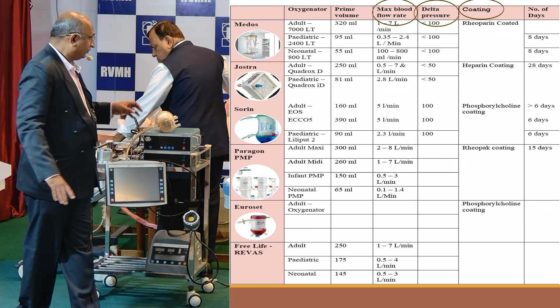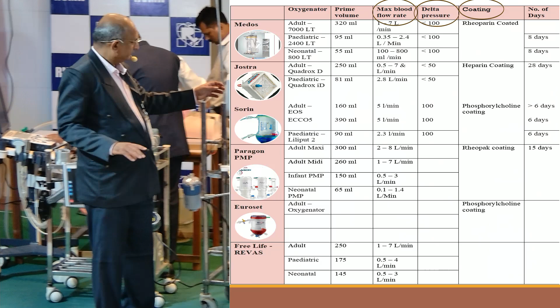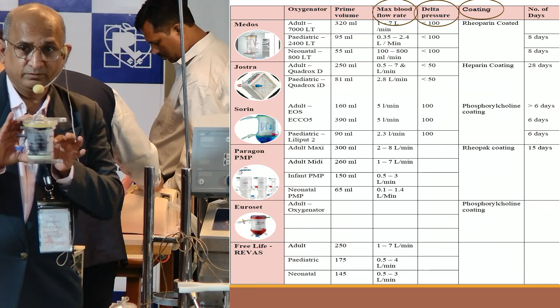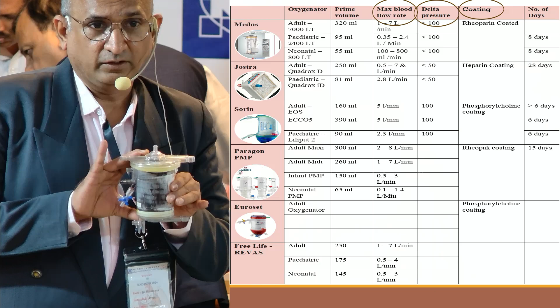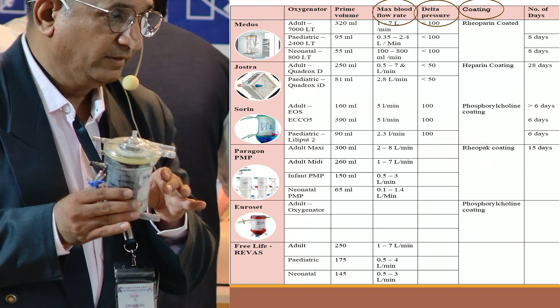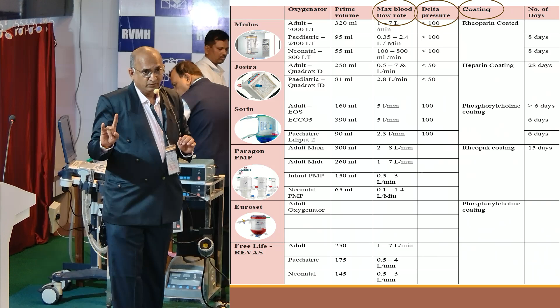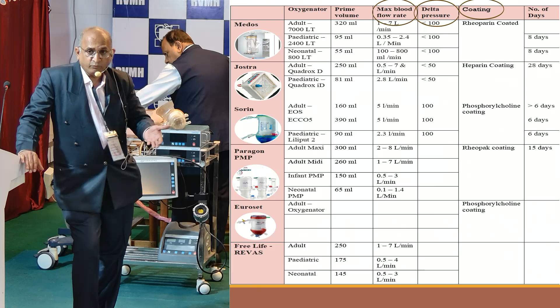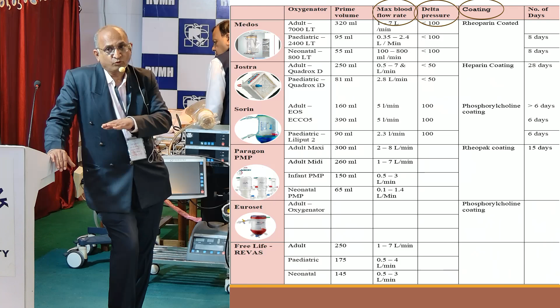So you have to use the appropriate oxygenator. For example, as I showed you, a pediatric oxygenator. Suppose you want to support neonates, you require such a small oxygenator. You don't require a big oxygenator, and it can support you for 800 ml. This can be used even for ECMO, because in ECMO we are not going to go above 500 to 800 ml of flow. So this is good enough for that. But if you want 1.2 liters of flow, you can't use this. Then you have to put one more oxygenator. Most of the PMP oxygenators have a rated capacity of 7 to 8 liters except Sorin. Sorin oxygenator has a rated capacity of 5 liters only. So if you require 6 liters of flow and the oxygenator is Sorin, you have to put an additional oxygenator.